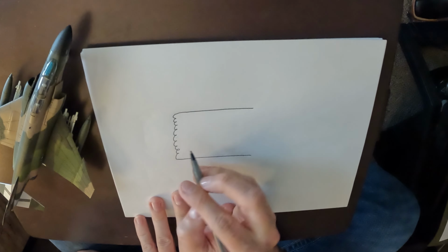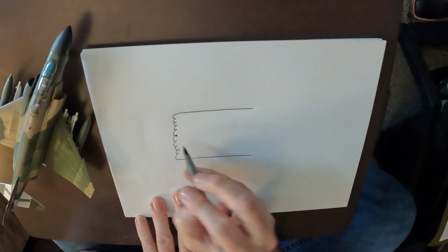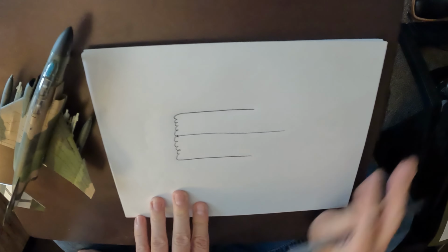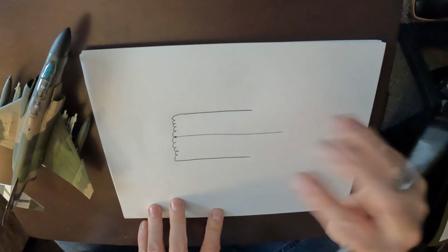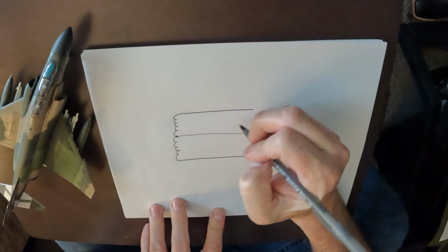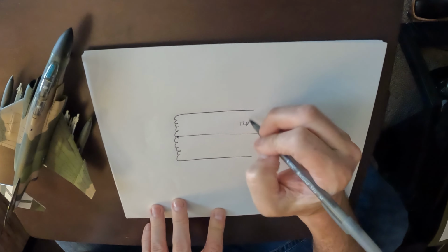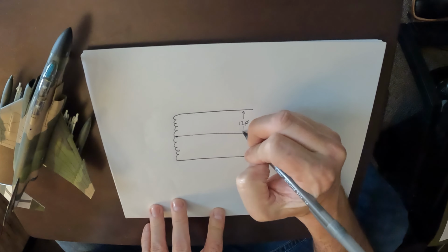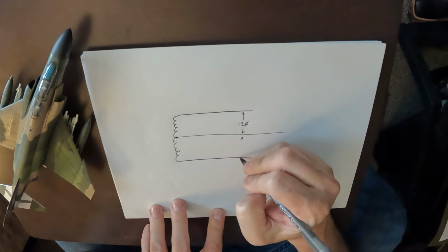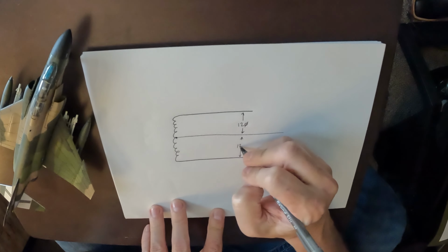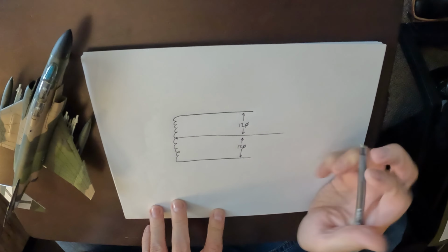Well, if we center tap the coil like so and split it, you're effectively splitting it in half electrically. And one half of the coil will create 120 volt from here to here. The other half will also create 120 volt from there to there.